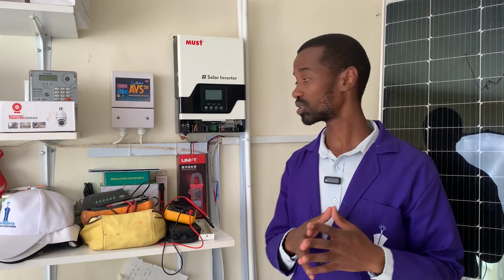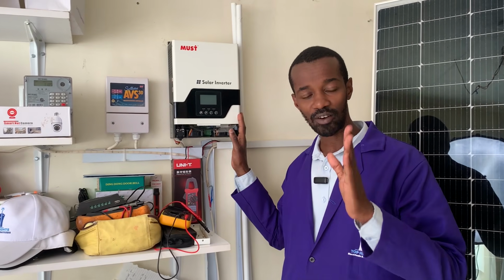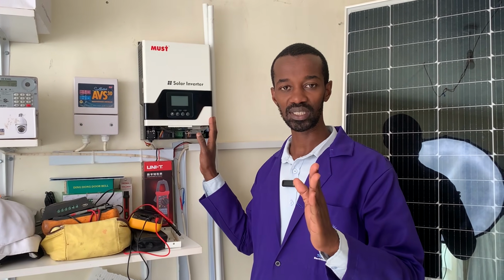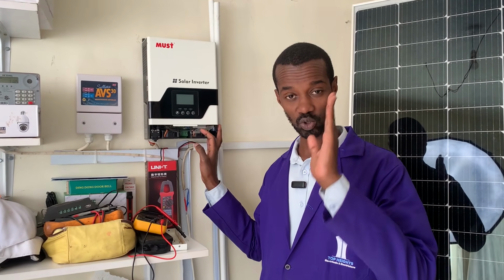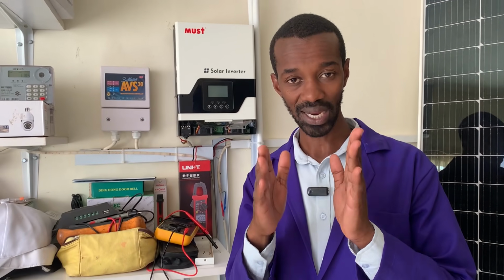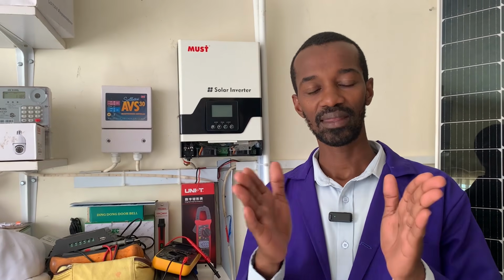Another reason why we need to do that is because this inverter has a specific voltage it is supposed to operate on. A 1 kilowatt inverter is connected to a 12 volt battery or a 12 volt system, and a 3 kilowatt inverter is connected to a 24 volt system. A 6 kilowatt is connected to a 48 volt system, and this is what we refer to as high voltages.